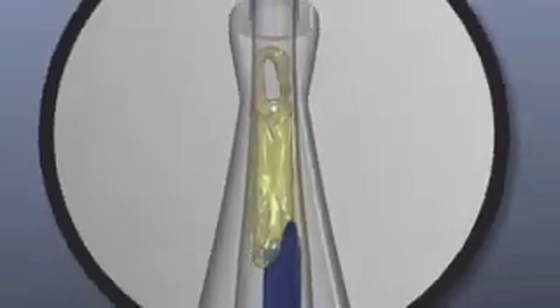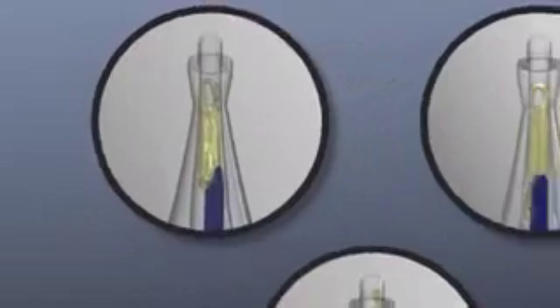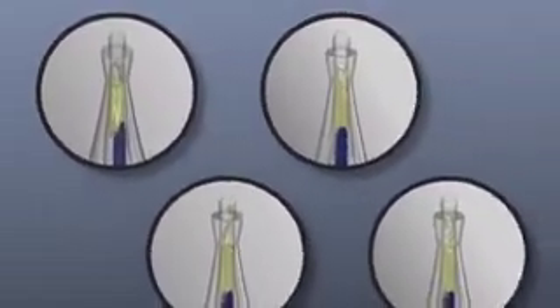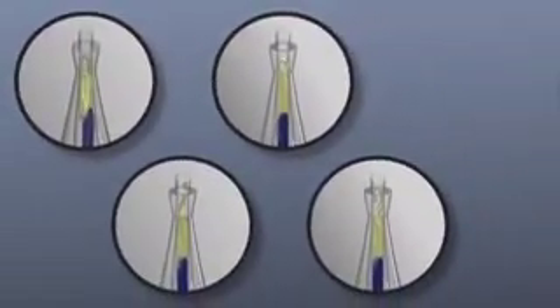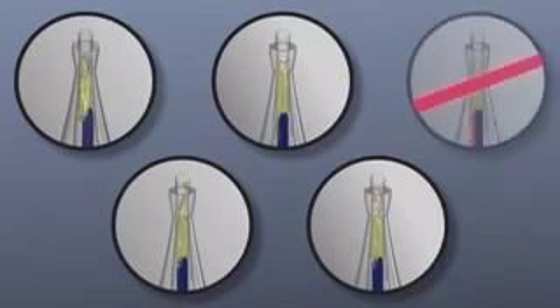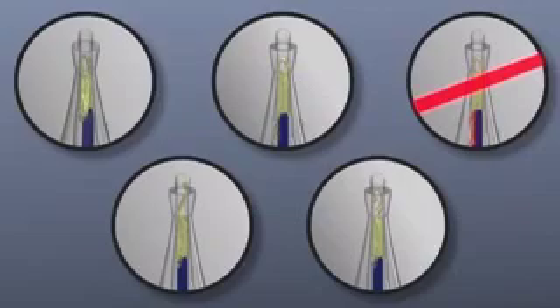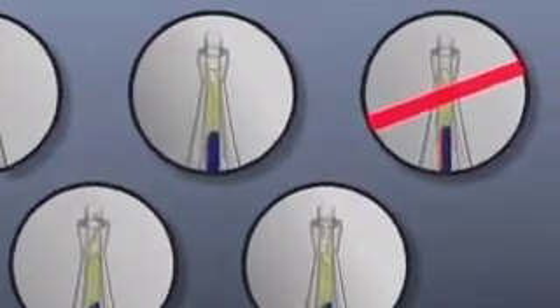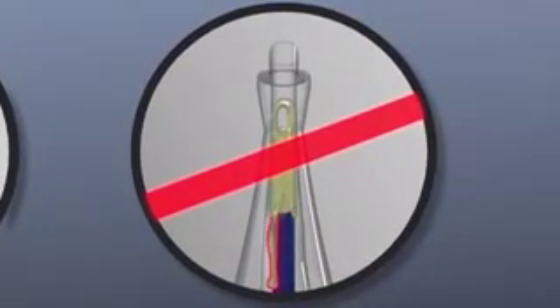Once the correct position of the plunger is confirmed, inspect both the leading and trailing haptics per the package insert. Depending on the temperature and the rate of plunger advancement, the haptics may take on various normal configurations. The range of normal haptic configurations and the only known do not proceed configuration is displayed in the package insert. The do not proceed configuration occurs when the trailing haptic extends straight down from the optic. Since this trailing haptic is trapped, the IOL cannot be fully delivered, so implantation should not be attempted.